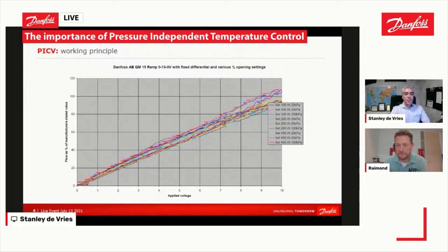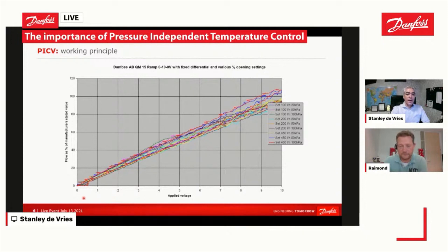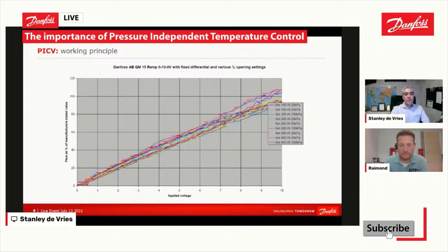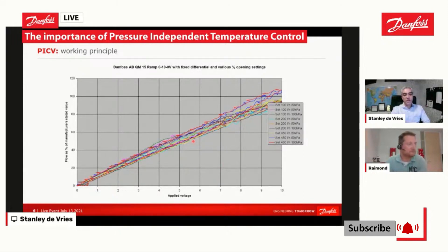If we look at this graph, on the bottom we see a 0 to 10 volt control signal and here we see the actual flow. The different colors of lines basically represent different settings of the valve and also different pressures — so different available pressures.